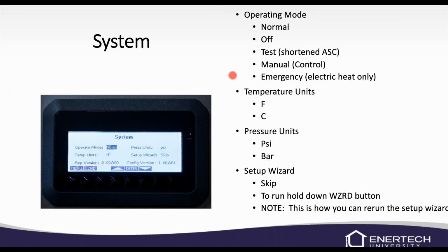The system, here you can go in here and test it. Normally, obviously, you'll be in normal mode. You can turn it off if they're going to be gone or something and they don't want the unit running at all. You can put it in test mode, which will speed up your anti-short cycle. You can put it in manual mode and control your compressors and pumps and things like that for diagnostics. You can also put it in emergency mode if the compressor were to fail. You can put it in emergency and then it'll run on electric heat only.